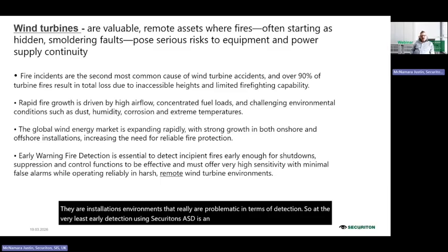So at the very least, early detection using Securiton's ASD is an absolute must. We can detect really very early, up to 1,000 times more sensitive than a typical point detector. At the very beginning of a fire incident, our ASD can detect that fire at its early stage, and then in conjunction with a suppression system or other means, we can help minimize the damage, potentially avert a disaster, and keep the wind turbine running, or get it back up and running quickly, so we're able to keep our promise to provide renewable energy.